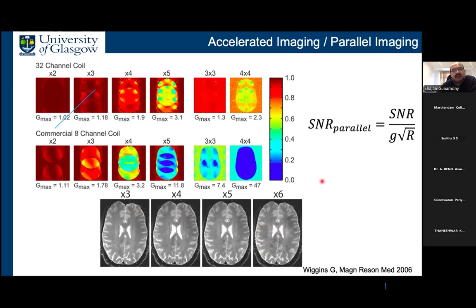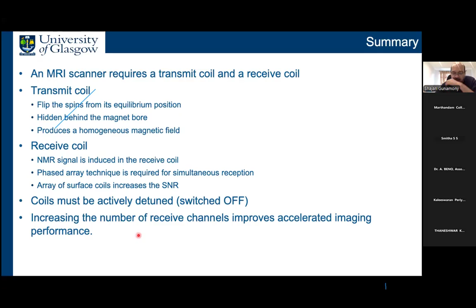In an MRI scanner, you need these two coils, a transmit and a receive. The transmit coil flips the spin from the equilibrium position. It's always hidden behind the magnet bore, and it produces a field which is very homogeneous. The receive coil is to pick up the MR signal, and with the NMR phased array technique, we can simultaneously receive the signal from a larger field of view, and if you use an array of these surface coils, you can increase the signal to noise ratio. I also spoke about active detuning, which is to switch on and off these coils. And increasing the number of receive channels will improve the accelerated imaging performance.